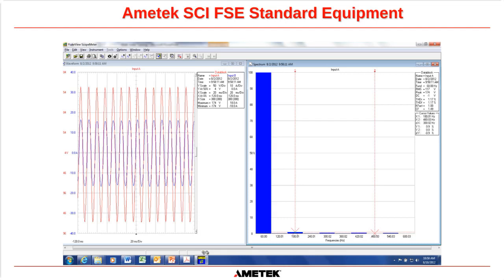Be very careful if your guys are using non-isolated oscilloscopes. That can go very badly. You don't want to do that. Somebody has asked, is the risk worth it to simulate a total power loss just to see if the UPS will pick up the load?